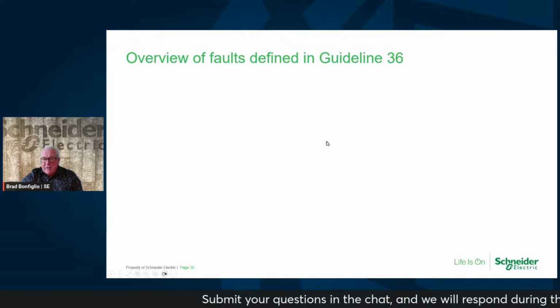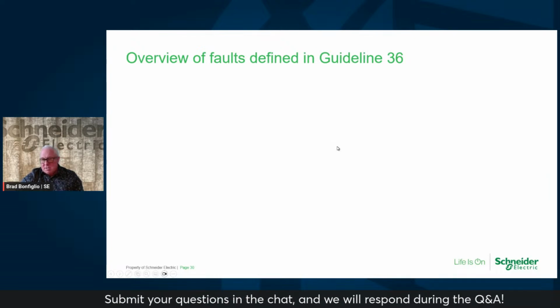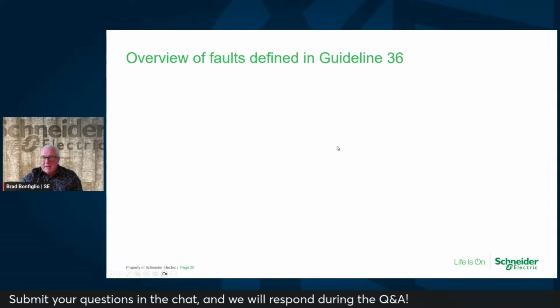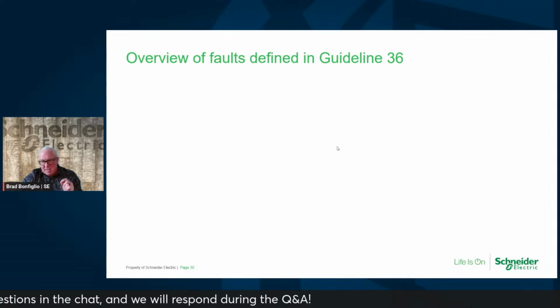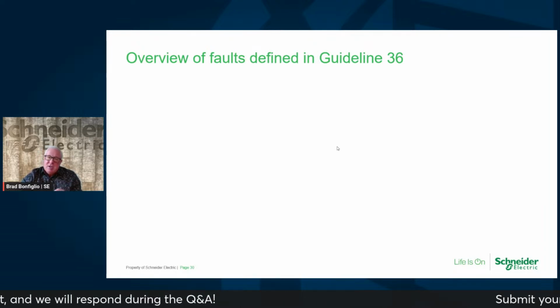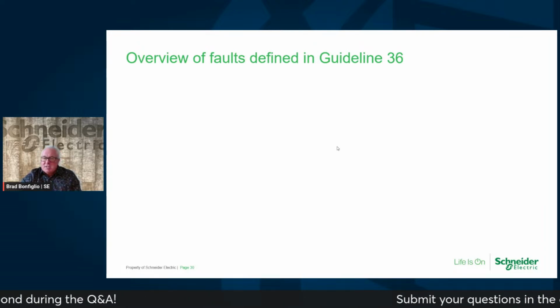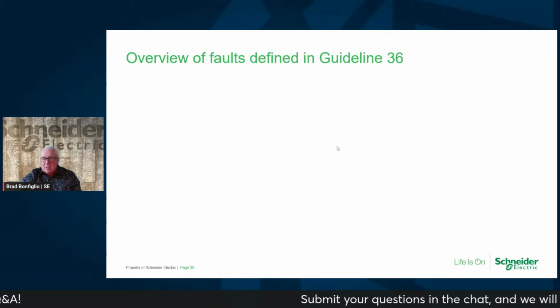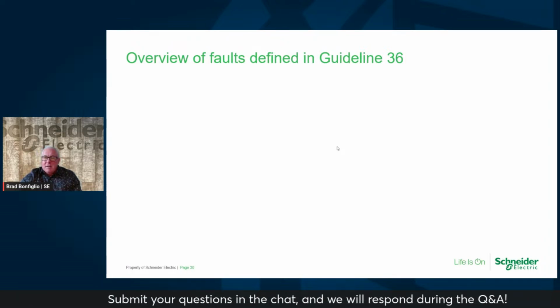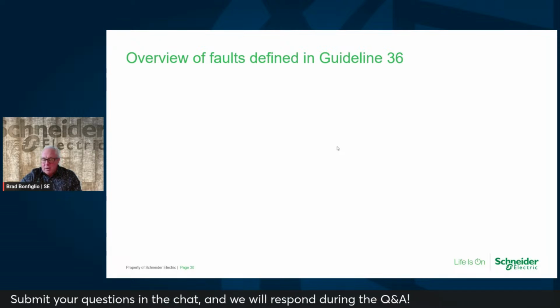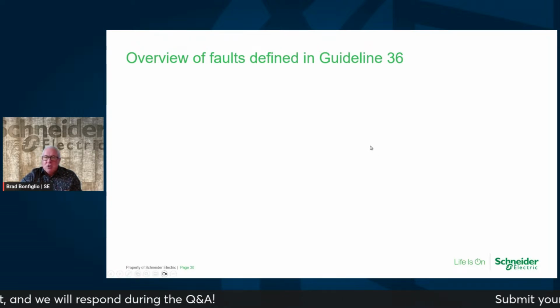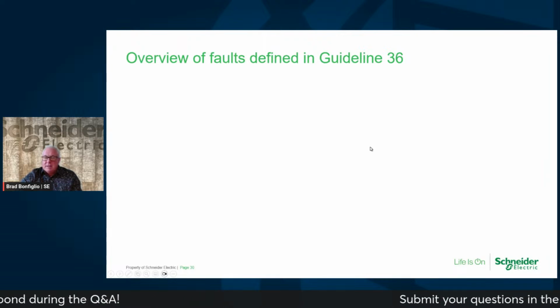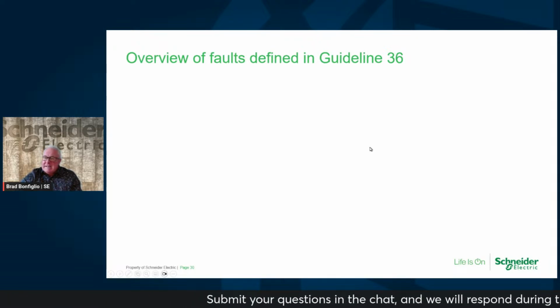So how do we define the faults? This is another big deal within Guideline 36. And I'm going to say Guideline 36, but actually if you follow ASHRAE's 90.1 2016 or greater or sooner, you will find fault detection is also part of that guideline as well. Okay, so this is nothing new other than they've expanded the list of faults than what the ASHRAE 90.1 has.